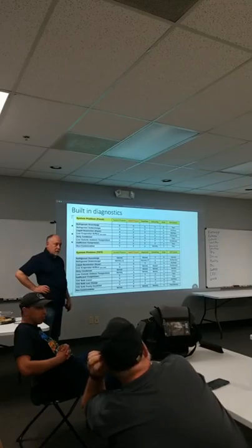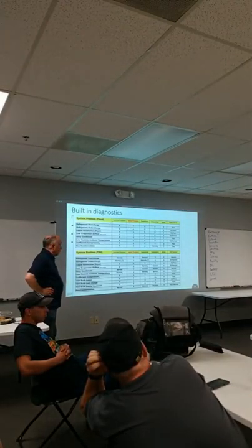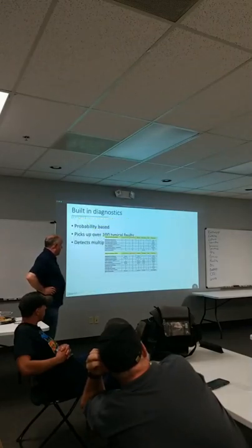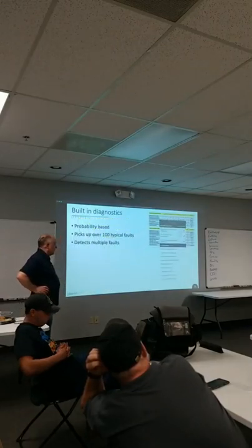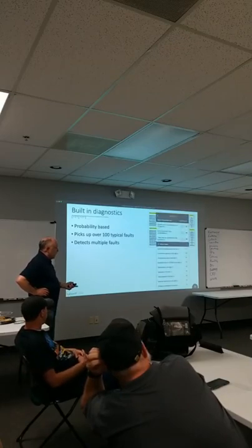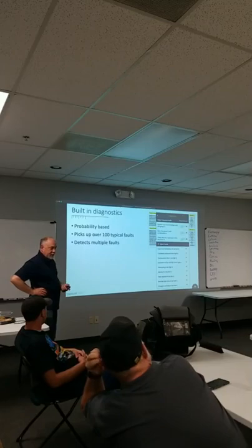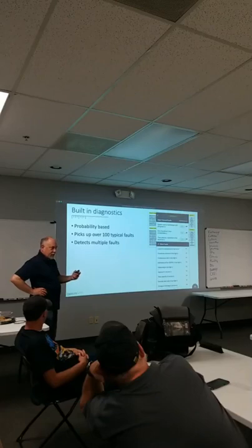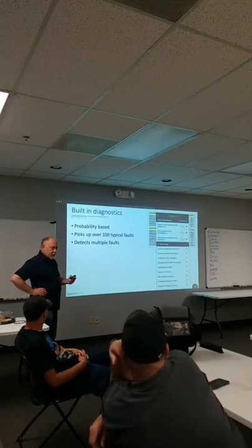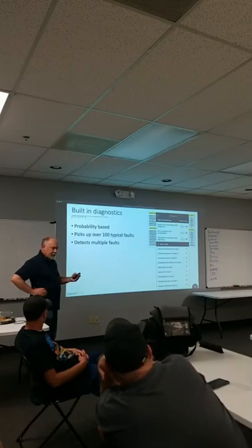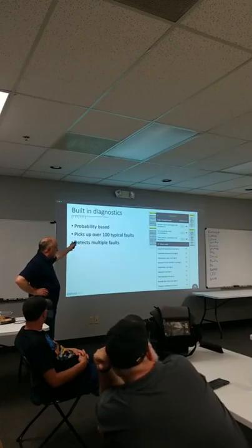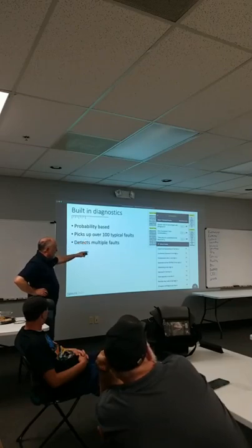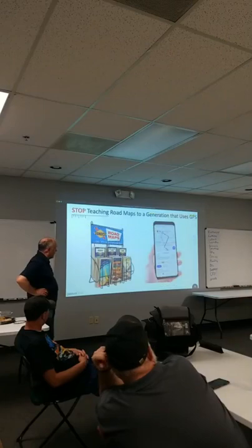That's what I always liked about those charts. Higher than normal this, lower than normal that, but how do you know where normal is supposed to be? Even with 2 identical pieces of equipment, how they're installed and everything else affects that. This is why we benchmark equipment and capture the personality of the system, because every system that we install is a function of its installation. The duct system, the power supply, the line set length, the filter type, every single one is characterized by its installation. The idea is that if we can dial in how that piece of equipment is supposed to operate, then when things change, we can start to pick out the faults.